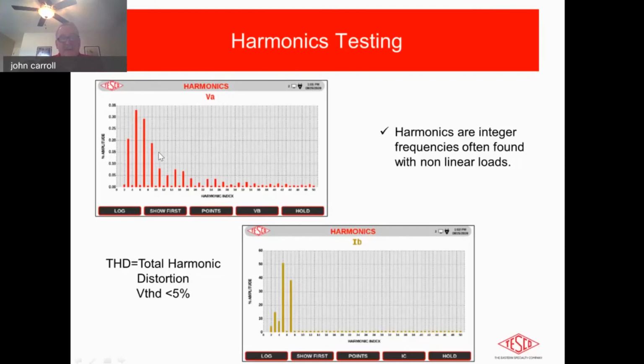So the important part about this is, what is the effect? Harmonics are just around us all the time. They are a natural phenomenon that's almost created by load conditions and different types of loads. I'll talk a little bit about that in a second. But the takeaway I would give you from this is, overall, without going through a whole algorithm chart here, you can see there is a sinusoidal component to this. If you look at the harmonic index on the top left one, on the amplitude there, you'll see the second harmonic is that little one on the bottom there. Then you've got the third, 4, 5, 6, 7, and so on.